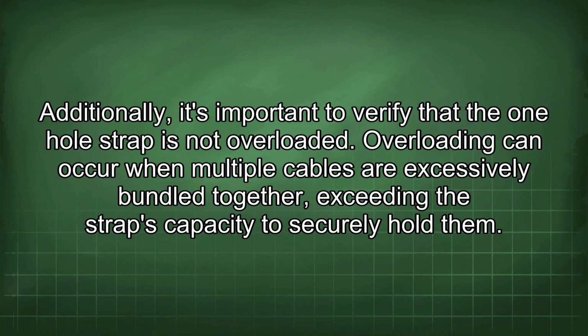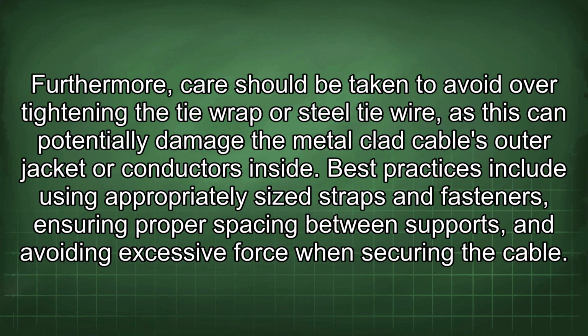Additionally, it's important to verify that the one-hole strap is not overloaded. Overloading can occur when multiple cables are excessively bundled together, exceeding the strap's capacity to securely hold them. Furthermore, care should be taken to avoid over-tightening the tie wrap or steel tie wire, as this can potentially damage the metal-clad cable's outer jacket or conductors inside.